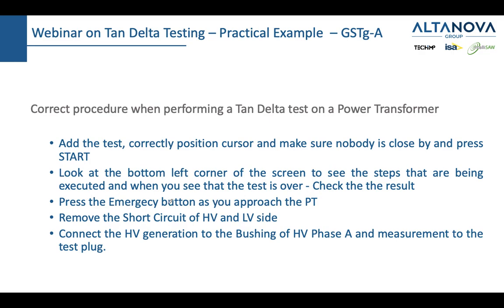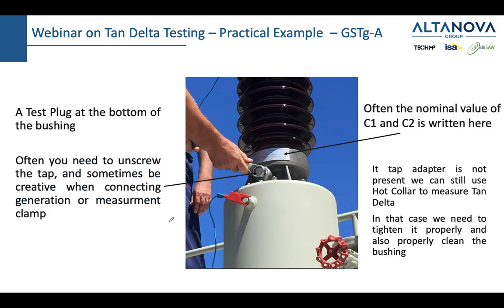You press the emergency button before you approach the PT, and then you start the next set of measurements. Before you do that, you remove the short circuit, because the next step is measuring the bushings. Now, bushings are actually more prone to insulation issues, and very often you just measure the bushings for tan delta. Maybe you don't even measure the body for tan delta, but you measure the body every 2 to 5 years, and bushings maybe every year.